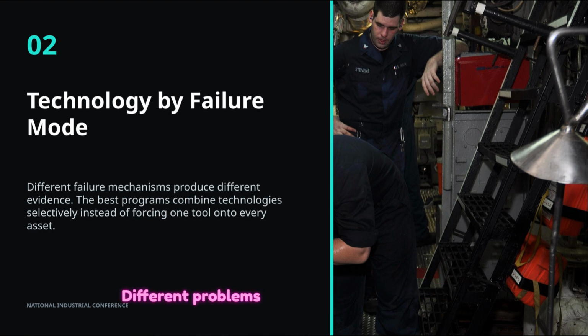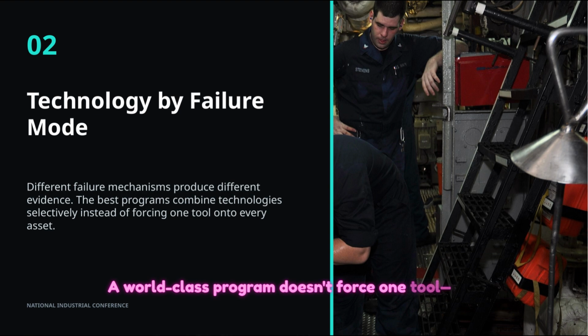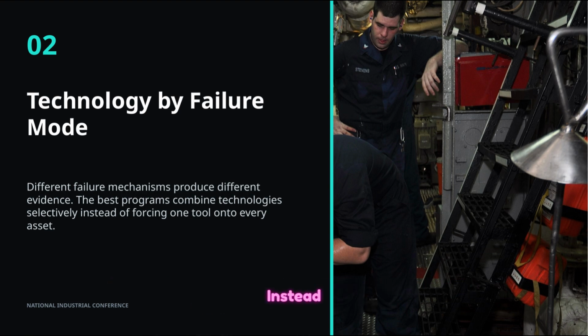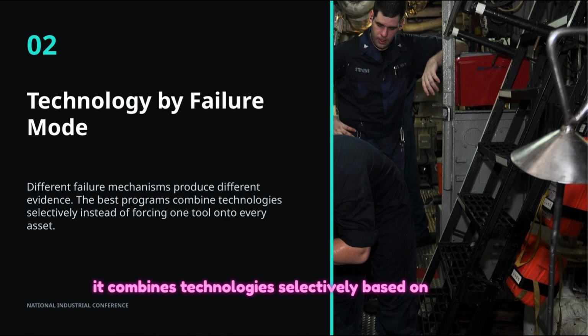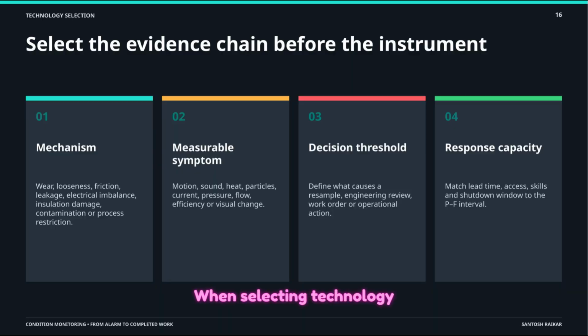Different problems leave different fingerprints. A world-class program doesn't force one tool, like vibration, onto every asset. Instead, it combines technologies selectively based on how the machine is likely to fail. When selecting technology, follow the evidence chain. Start with the mechanism. Is it wear, friction, or a leak? Then, identify the measurable symptom, like heat or sound. Define a threshold that triggers action. And finally, ensure your plant actually has the capacity to respond to that specific signal within the P/F window.